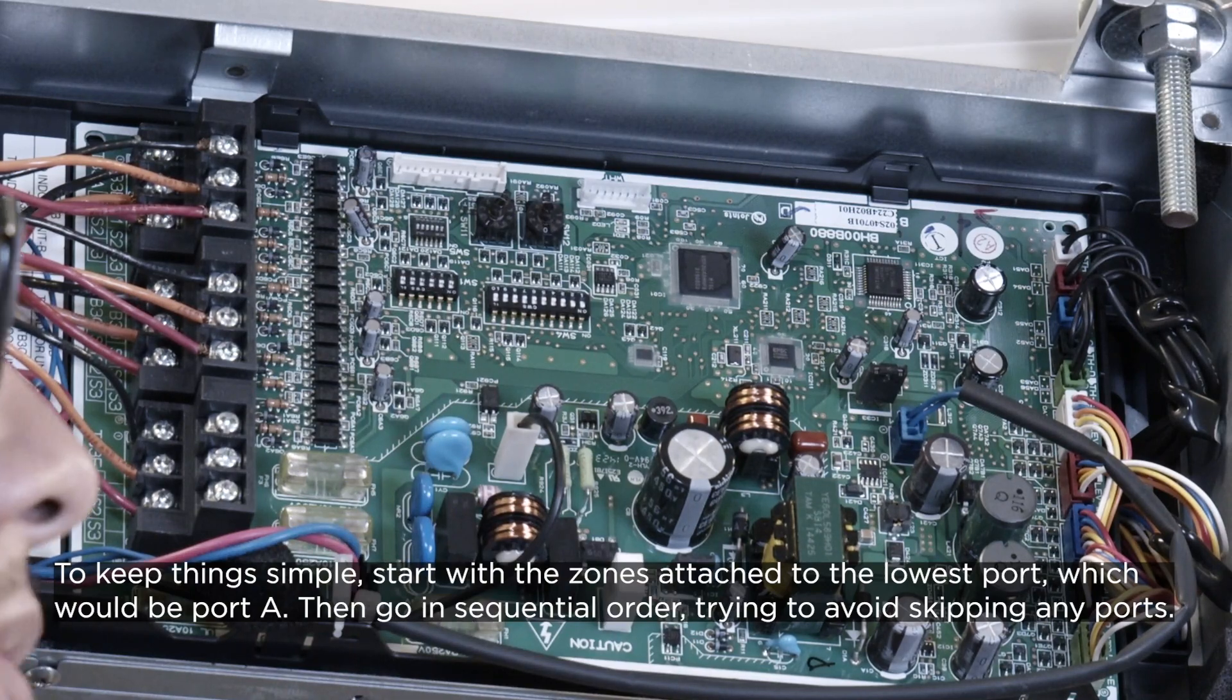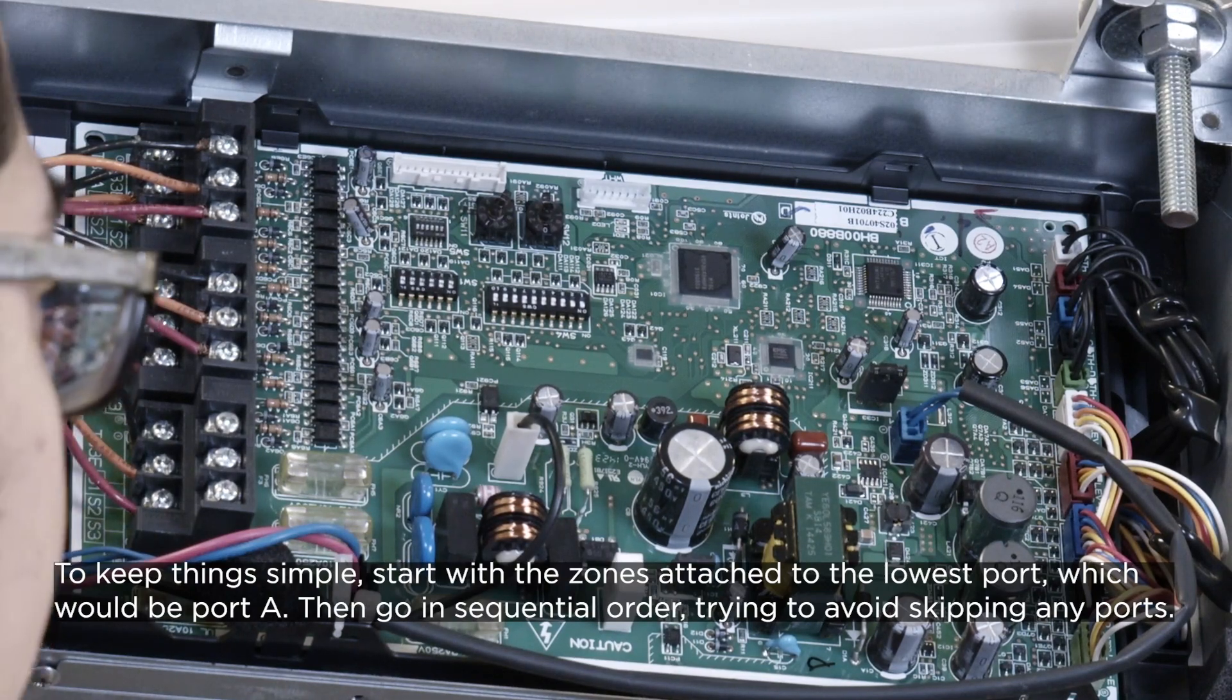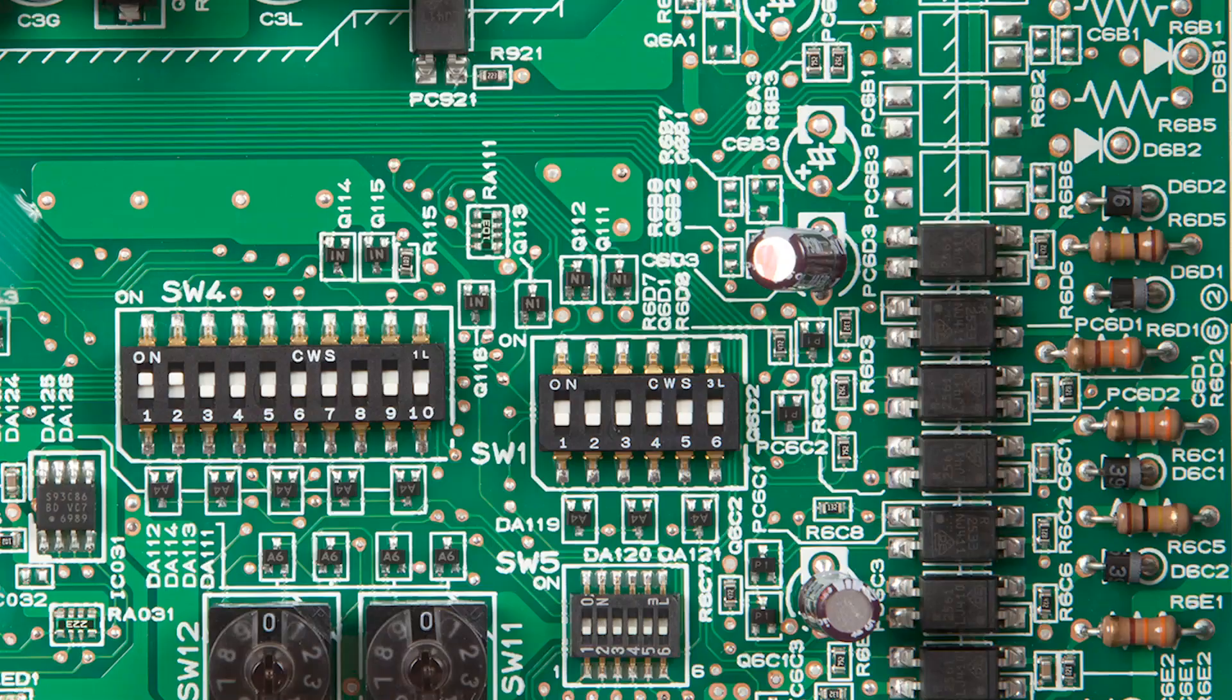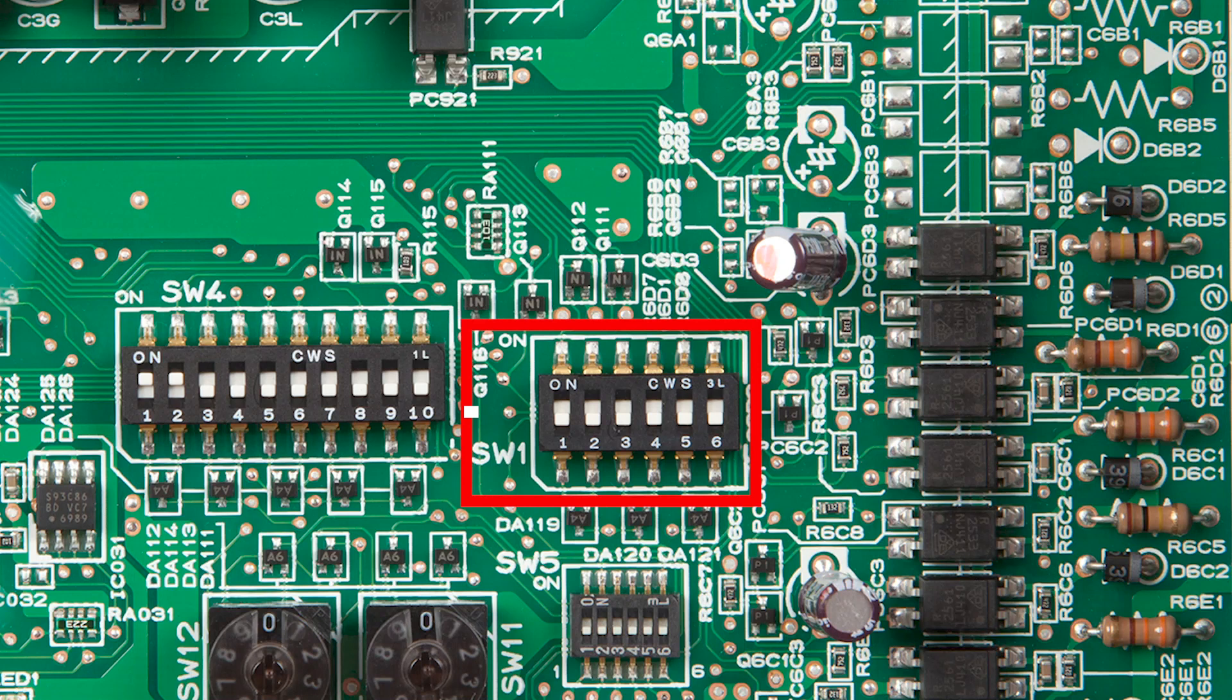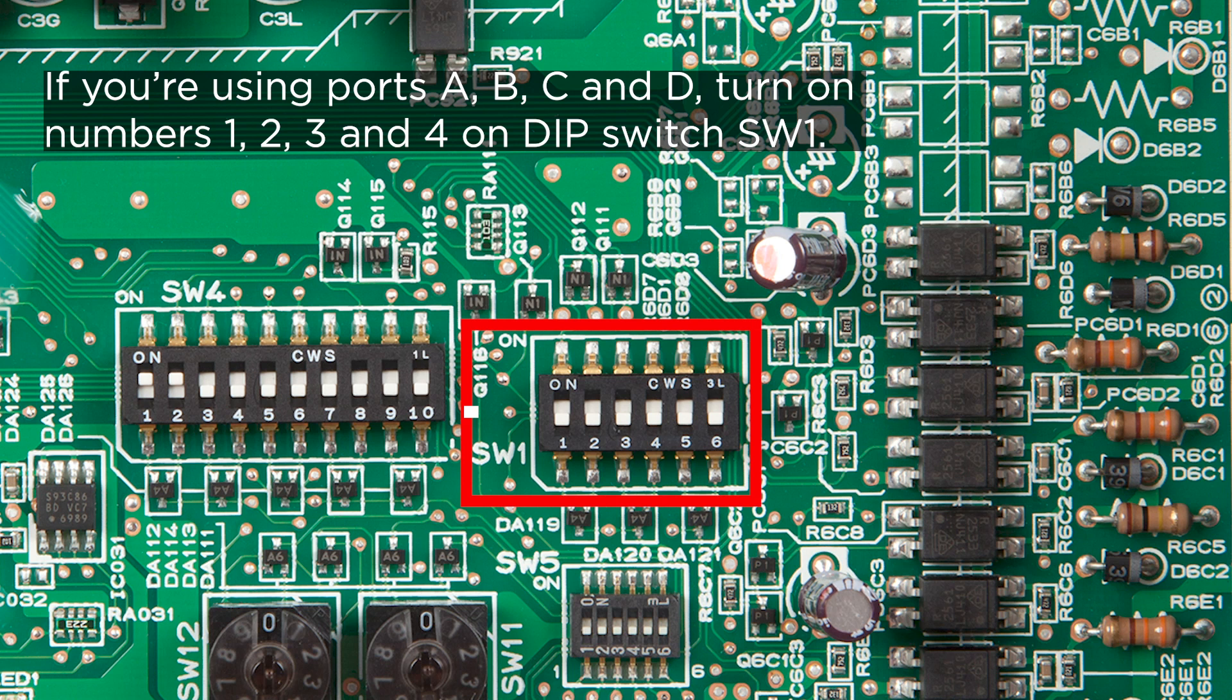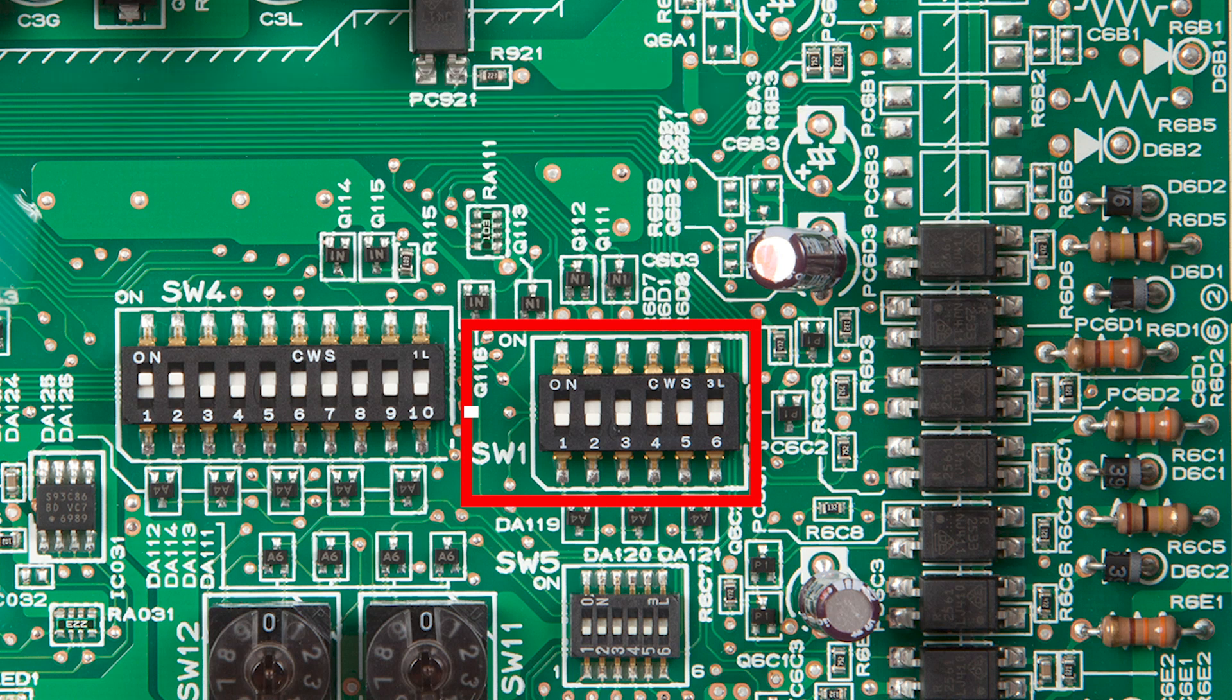For every zone that you have hooked up, you'll need to turn on the corresponding dip switch on SW1. If you're using ports A, B, C, and D, you'll turn on numbers one, two, three, and four on dip switch SW1. Turning on the corresponding dip switch will let the system know that there is a unit attached to that port.